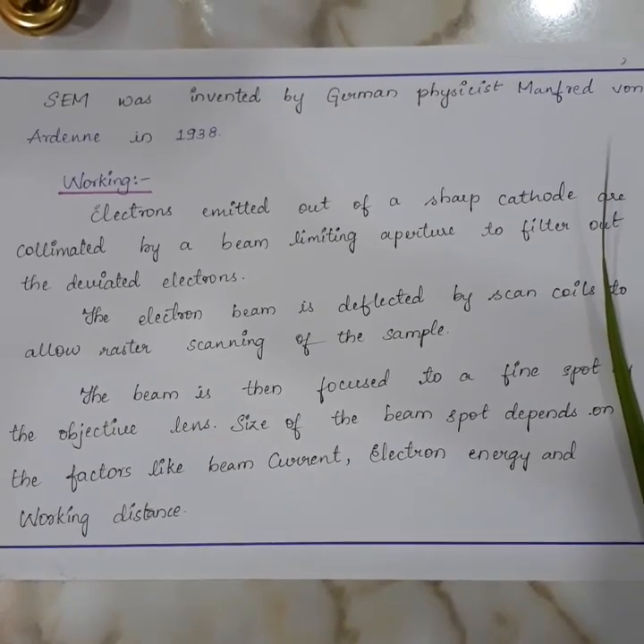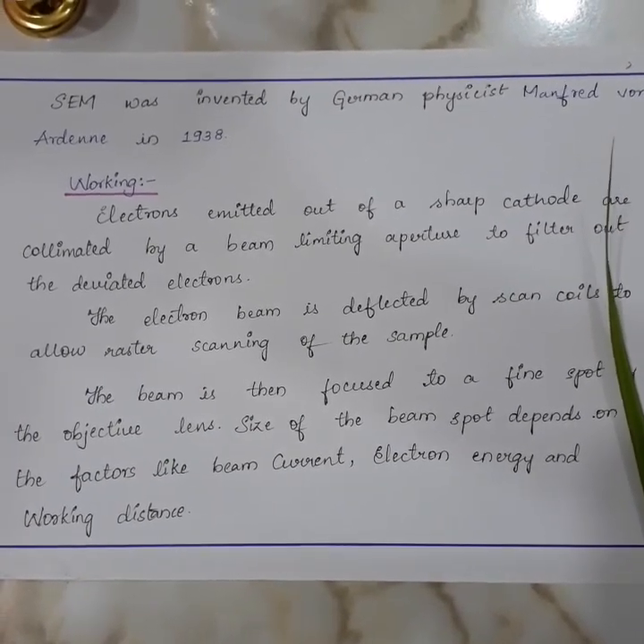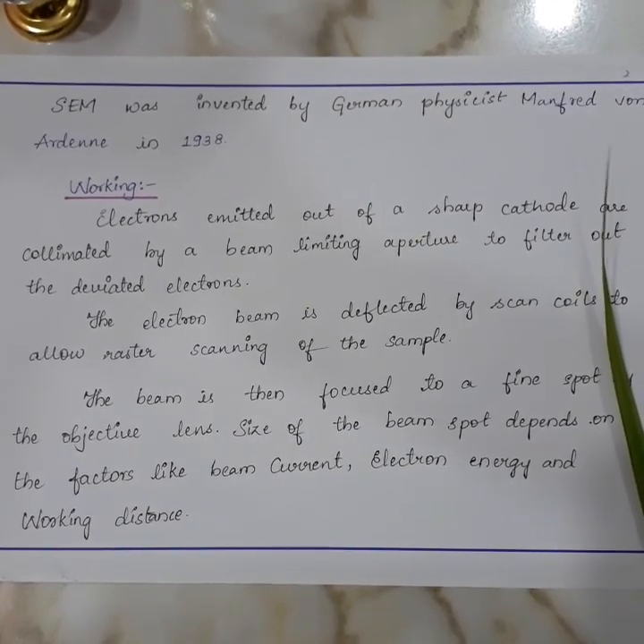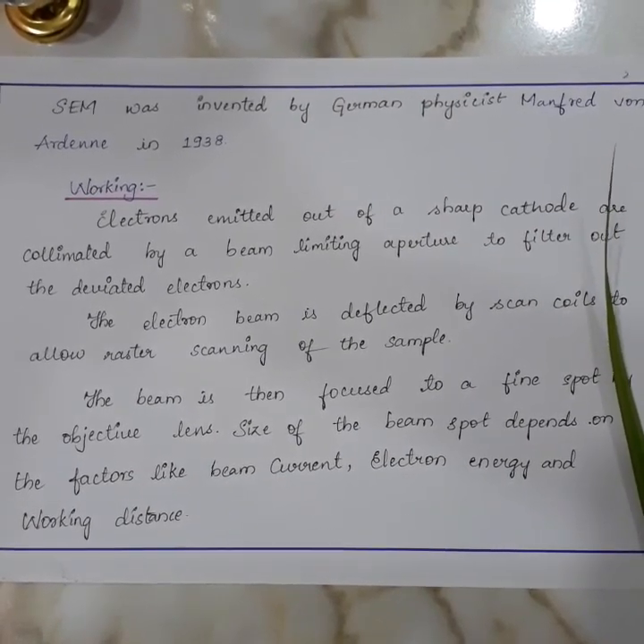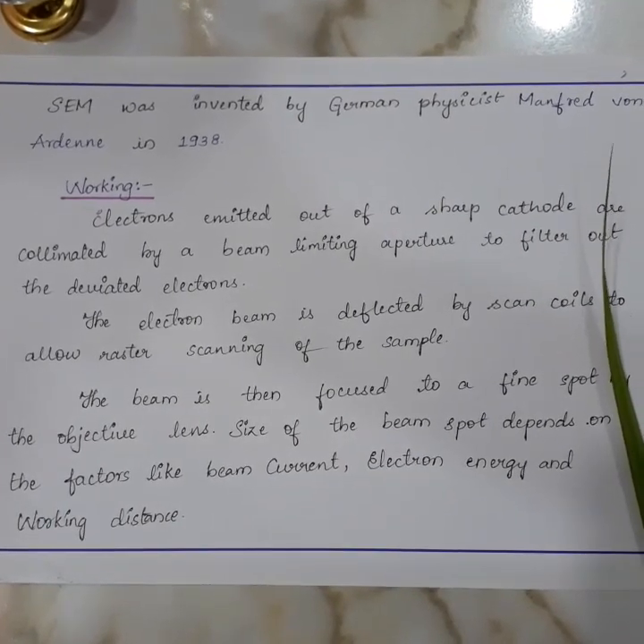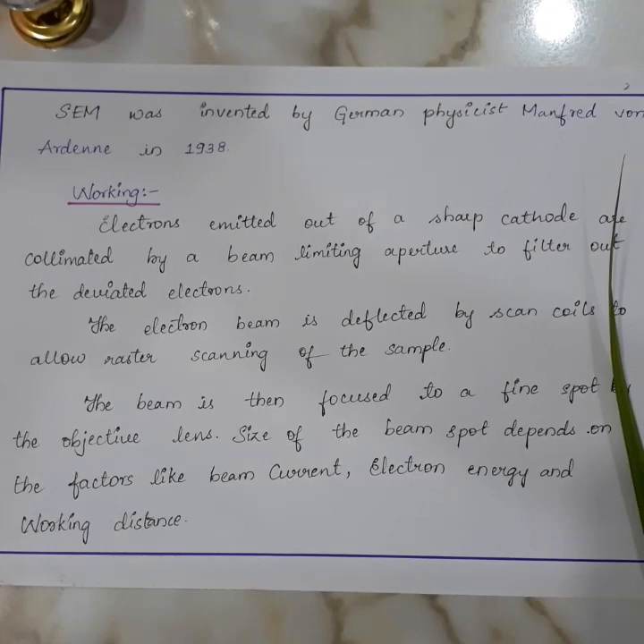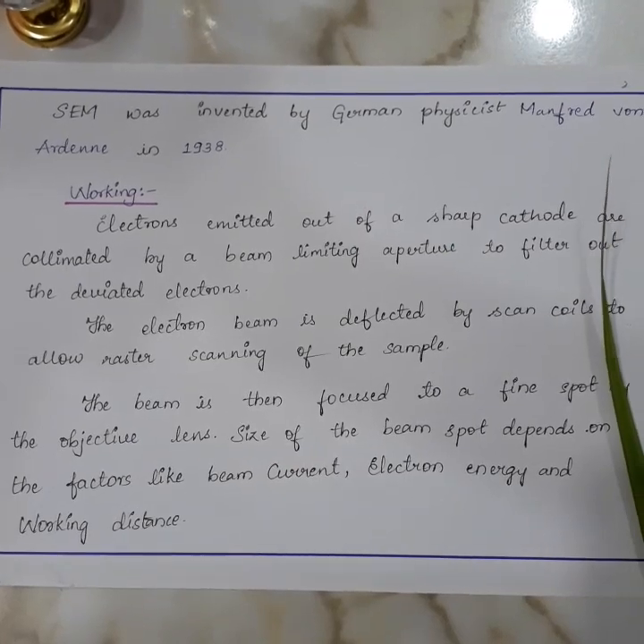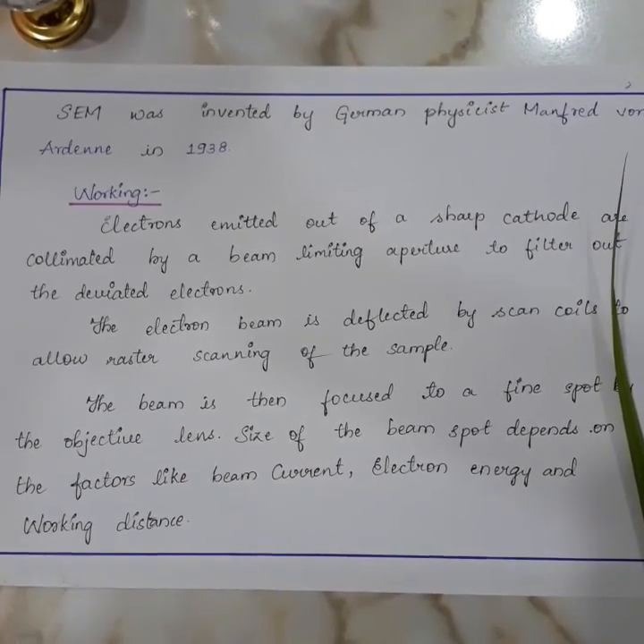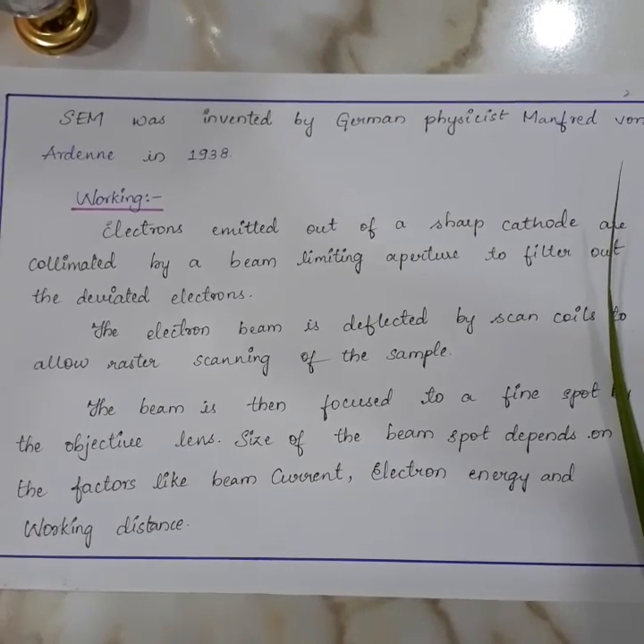Electrons emitted out of a sharp cathode are collimated by a beam-limiting aperture to filter out deviated electrons. The electron beam is deflected by scan coils to allow raster scanning of the sample. The beam is then focused to a fine spot by the objective lens.